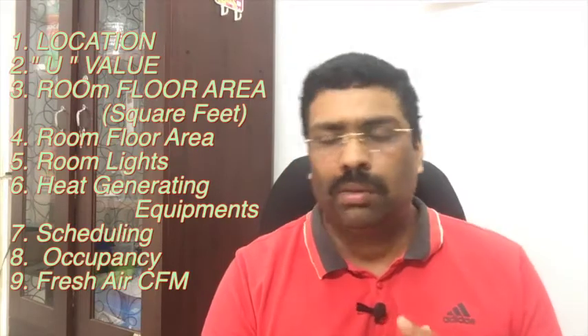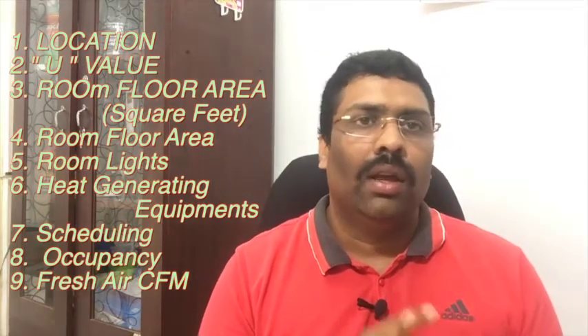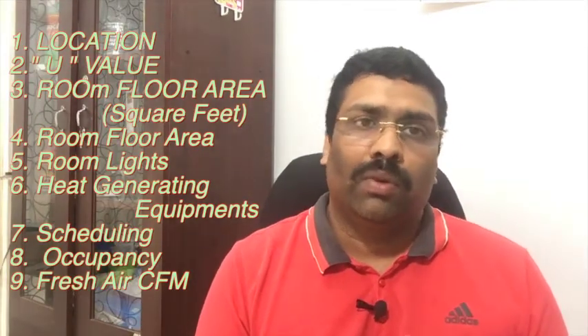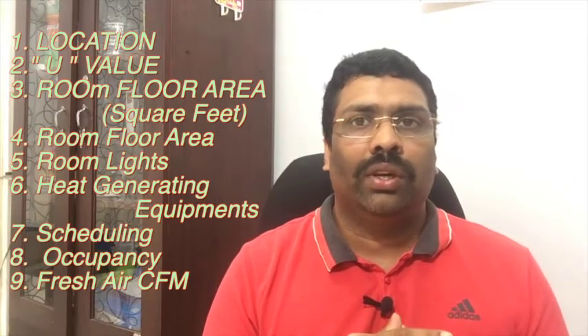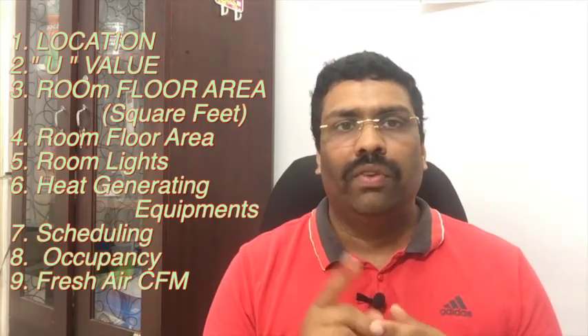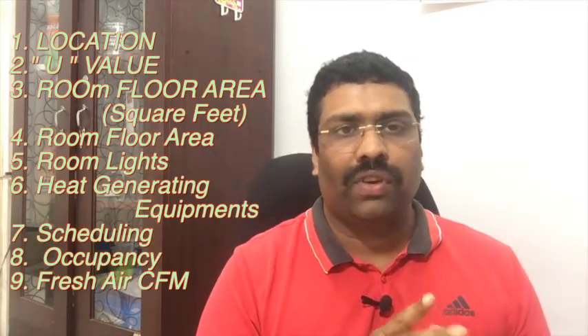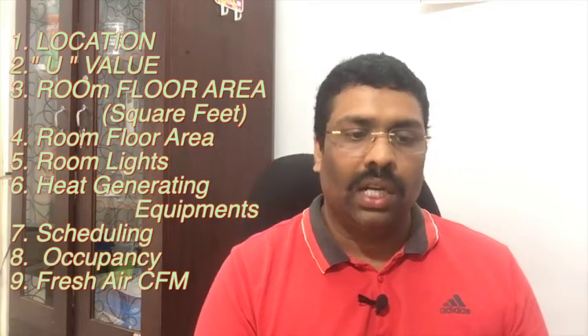So the ambient temperature of the fresh air will automatically come in, because we already mentioned the ambient temperature in the beginning. And how much fresh air we need to take from outside, that we need to enter. Normally 15 CFM per person is the fresh air quantity taken from outside the building. This is the 9th point.